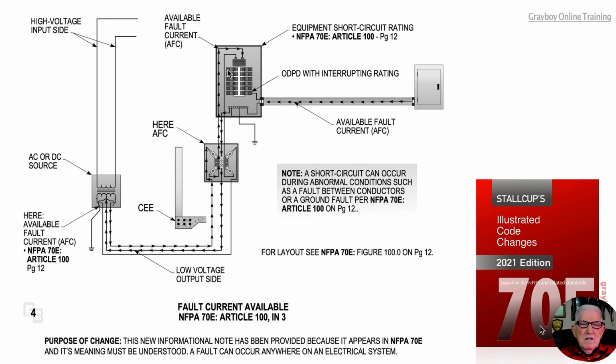So we sized this grounded conductor here back to this transformer in size for ground fault conditions based upon the size of these conductors. So as you know, as an example, if 4/0 conductors terminated to a 225 amp main, the minimum size of this grounded conductor here from our table 250.102(C)(1) in the NEC would be a number 2.